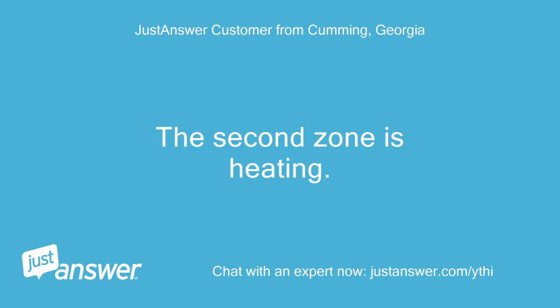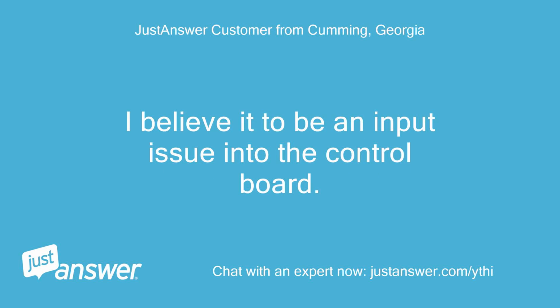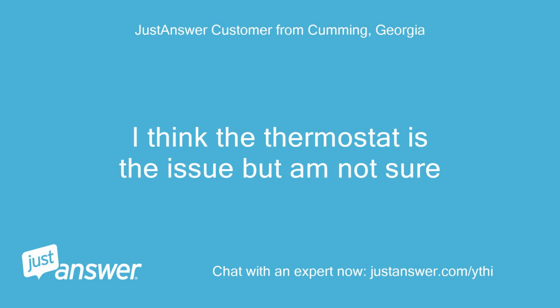The second zone is heating. The thermostat says cooling but hot air is coming out. I believe it to be an input issue into the control board. It is performing as instructed, but it is getting the wrong instructions. I think the thermostat is the issue, but I'm not sure.